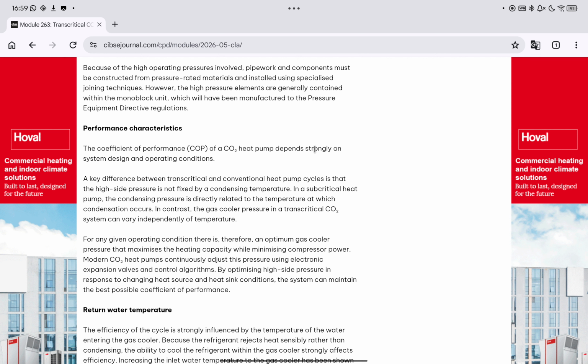In a subcritical heat pump, the condensing pressure is directly related to the temperature at which condensation occurs. In contrast, the gas cooler pressure in a transcritical CO2 system can vary independently of temperature. For any given operating condition, there is, therefore, an optimum gas cooler pressure that maximizes the heating capacity while minimizing compressor power. Modern CO2 heat pumps continuously adjust this pressure using electronic expansion valves and control algorithms. By optimizing high side pressure in response to changing heat source and heat sink conditions, the system can maintain the best possible coefficient of performance.